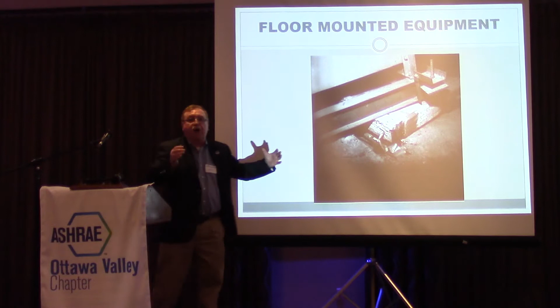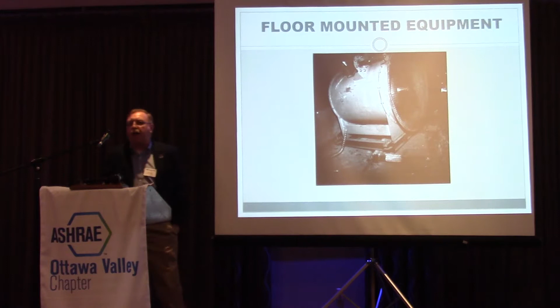So what they did is they had these concrete walls about 2.5 to 3 feet high that the fans would sit on, and they even had seismic restraints on them, vibration isolators, all that. Fine. The problem was they only put up two supports, one in the back and one in the front. So you stick this thing up 2.5, 3 feet in the air, and what have you done? All you've done is raise the moment on how much the thing's going to move. You have to brace these.